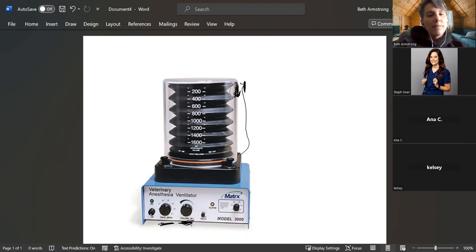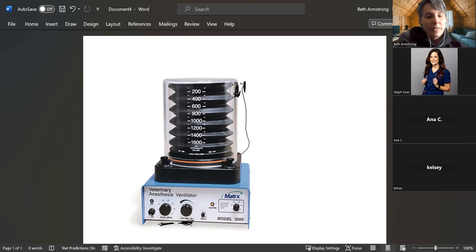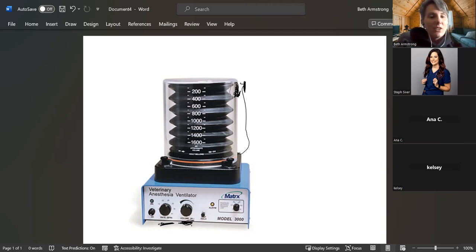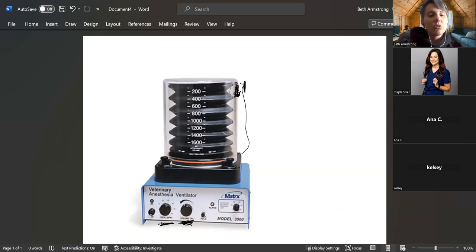And that's essentially how they're breathing rather than using our reservoir bag — this is essentially our reservoir bag. Oh okay, that's what I was wondering — is there a connection, or are you using the two at the same time? No, this is your reservoir bag replacement. So what we do from here — we have our volume that we can set and control, and then we can control the rate that we are giving their breath.